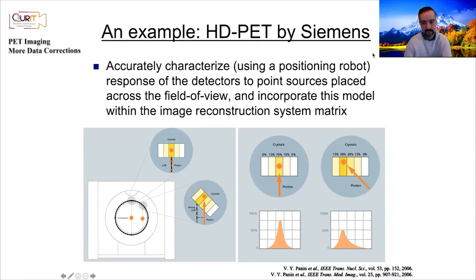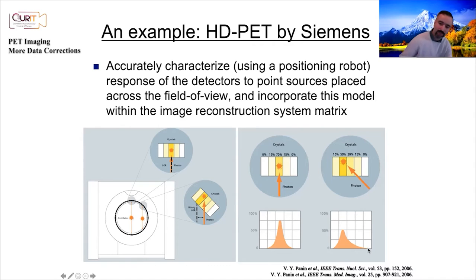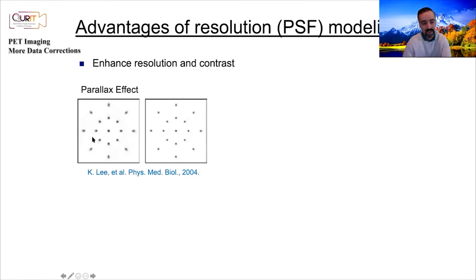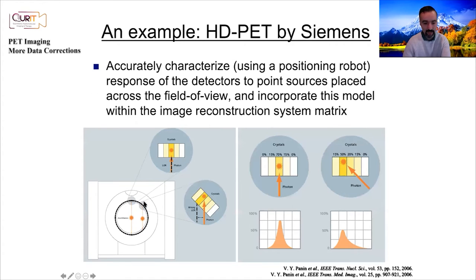Here's an example of how PSF modeling is characterized: a robotic arm moves point sources all over the field of view, measuring how the signal spreads. At 90 degrees you get one profile with scattering only; at an angle you get an asymmetric profile due to both scattering and penetration. This is modeled within image reconstruction. This PSF modeling approach addresses the parallax effect where resolution degrades as you move away from the center of the field of view.